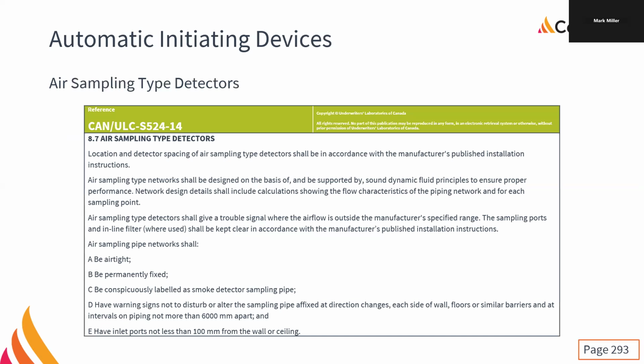Right, so we have some pretty significant limitations with these. There's not a whole bunch said in S524, the standard for the installation of fire alarm systems, about how to install the air sampling detectors. They mostly leave it up to the manufacturer. The big thing is the pipe work. The pipe network has to be airtight, permanently fixed, and conspicuously labeled.